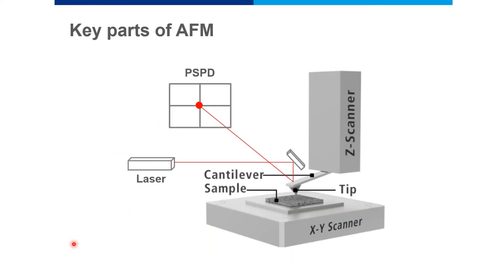The key parts include the cantilever with a tip at the bottom, a laser source that falls on the cantilever and reflects into something called a PSPD — a photosensitive position detector. There is a Z-scanner on which the cantilever is mounted, and the sample is mounted on an XY scanner. The XY scanner moves the sample in the X and Y directions, and the Z-scanner moves the cantilever in the vertical dimension.